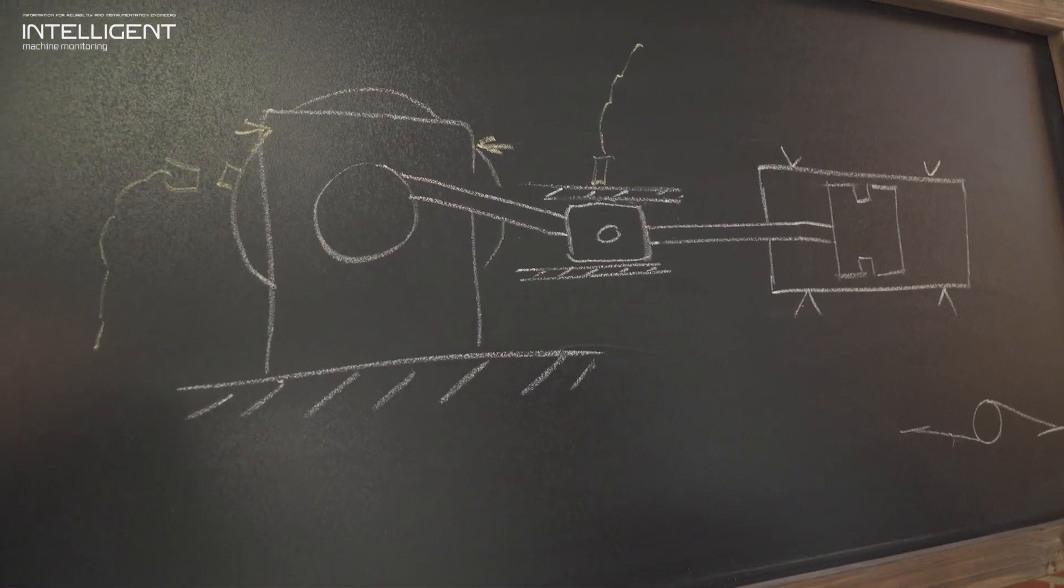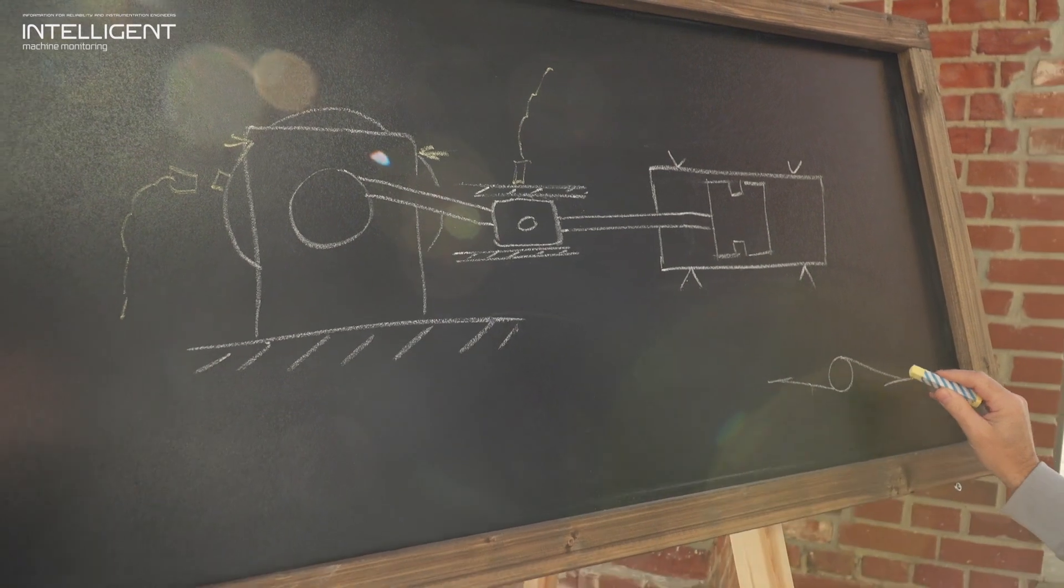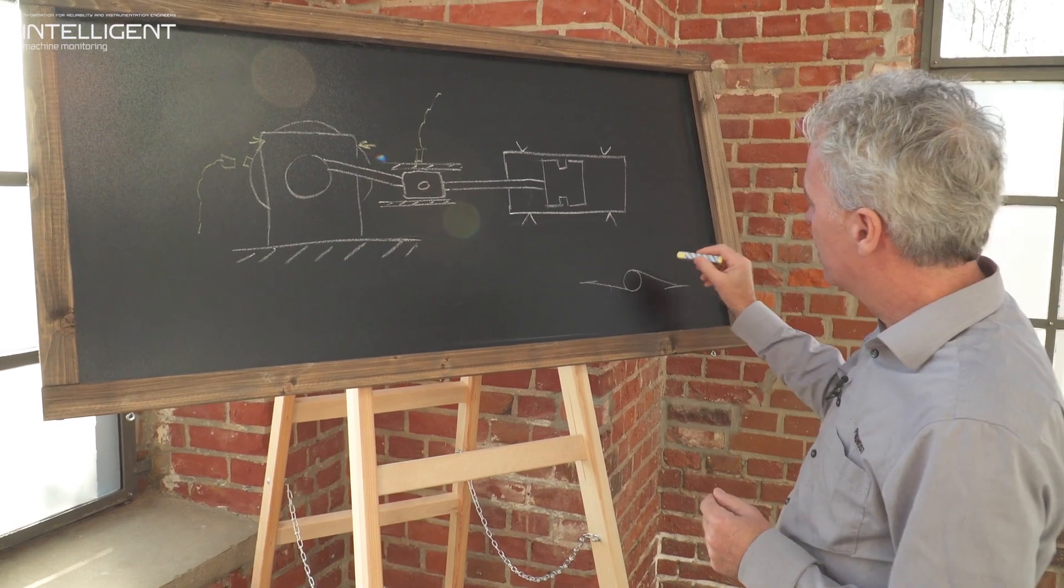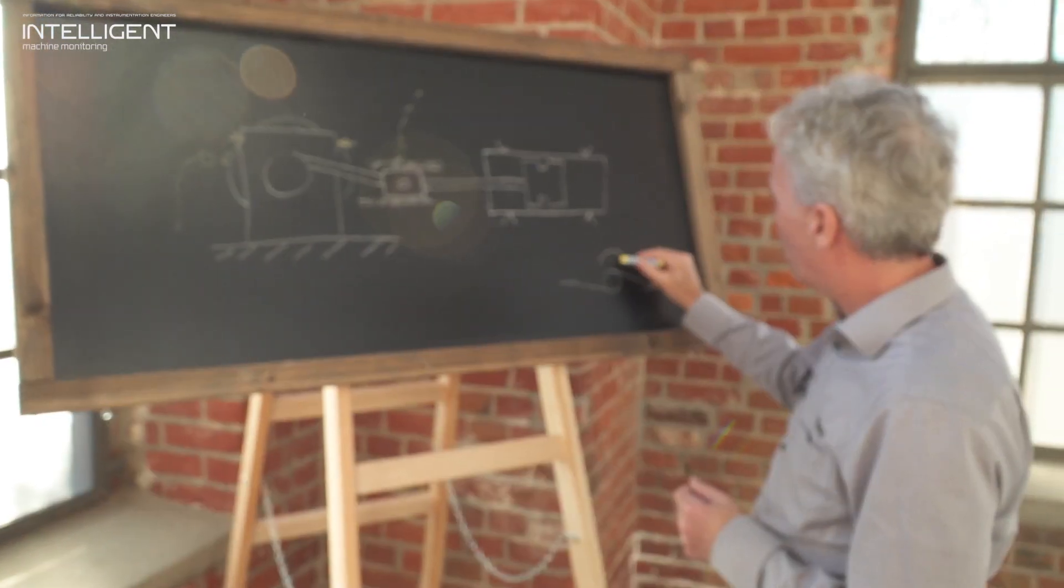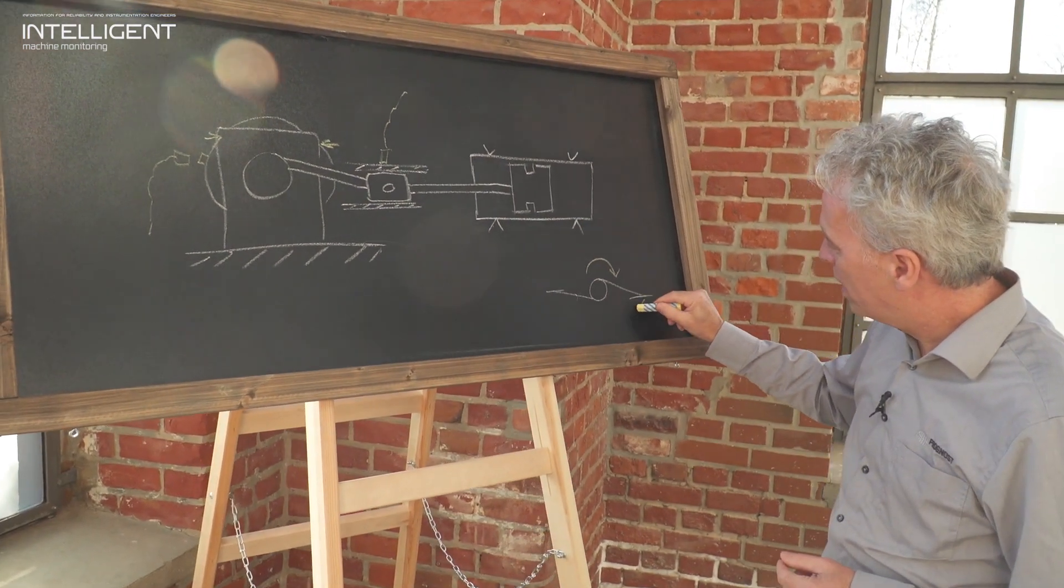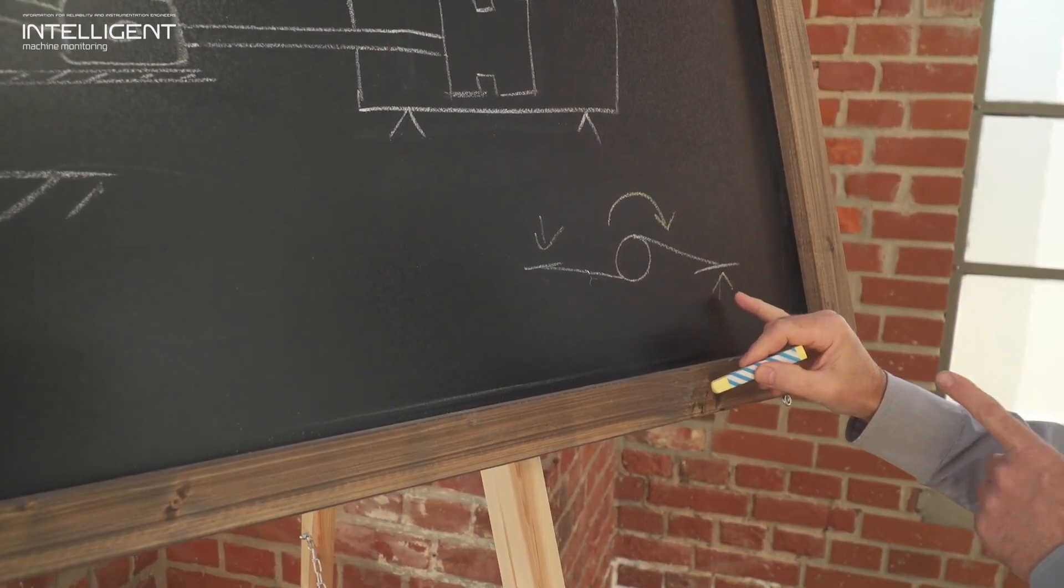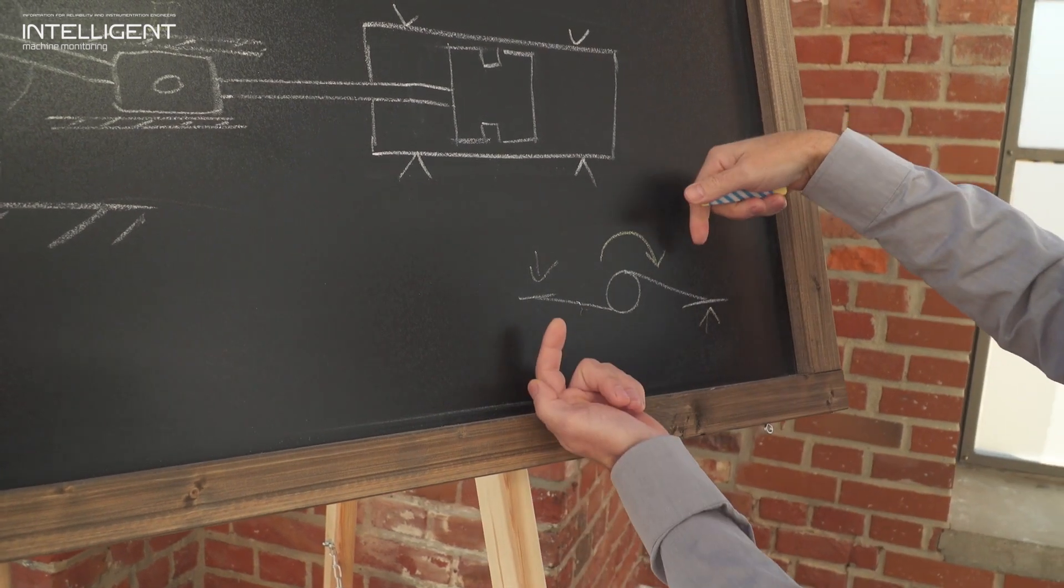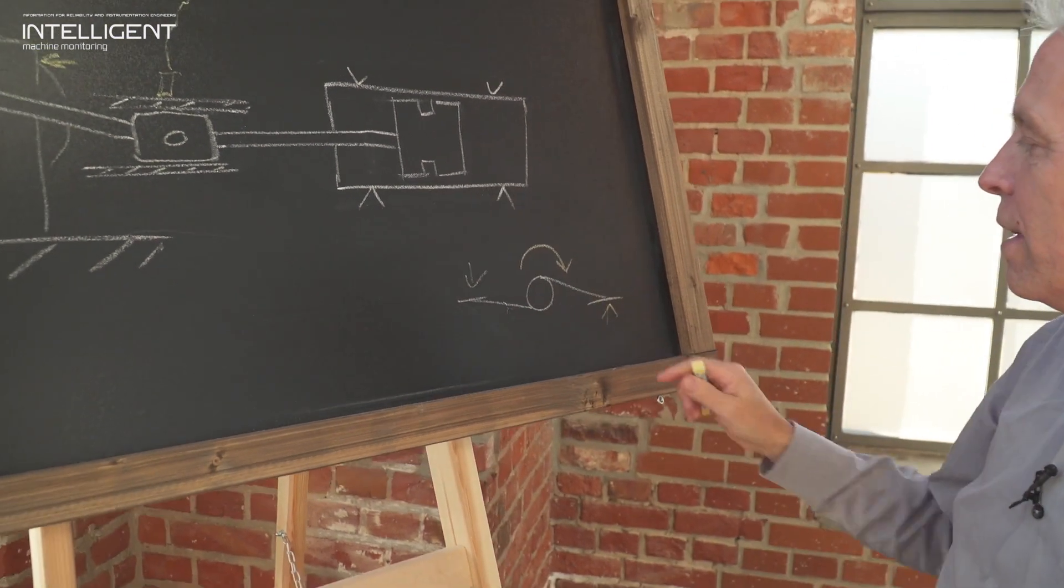The location of the acceleration sensor at the crosshead guide depends on the rotating direction of the crankshaft. The connecting rod only applies vertical forces to the crosshead guide, meaning if we have clockwise rotating direction, we would recommend to install the acceleration sensors below the crosshead guide here and here on top of the crosshead guide. In case the rotating direction is counterclockwise, we would install the sensors the other way around, provided that sufficient clearance is available beneath the crosshead guides.